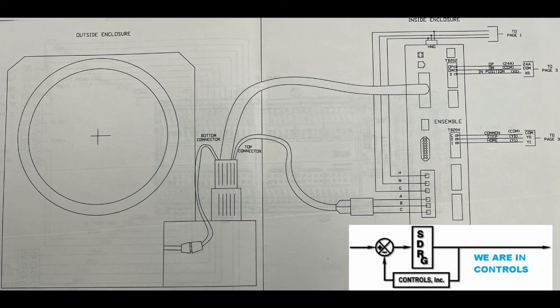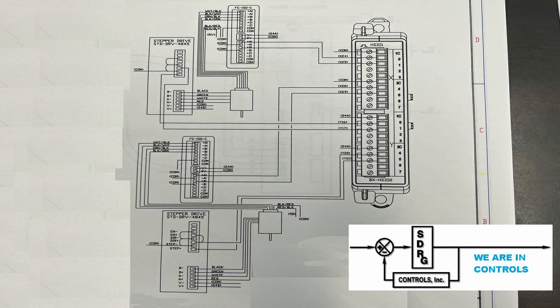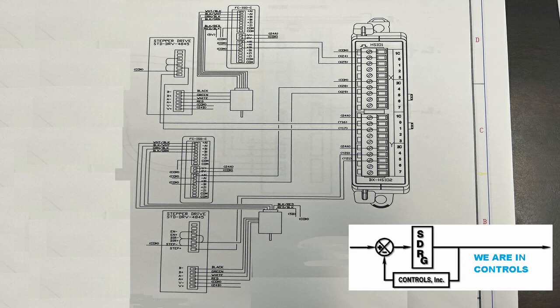All of these operations were controlled by a PLC programmable logic controller and an HMI man machine interface. This diagram shows the control of the two stepper drives that handled foil. One motor advanced the foil capstan and the other reloaded the foil. If the foil was present, the foil would advance a fixed number of counts to ensure fresh foil was available for the next increment of the turntable.